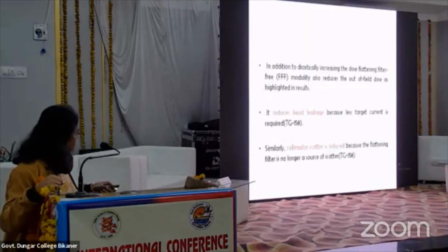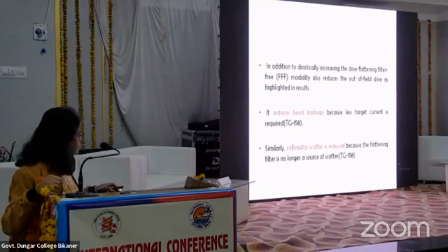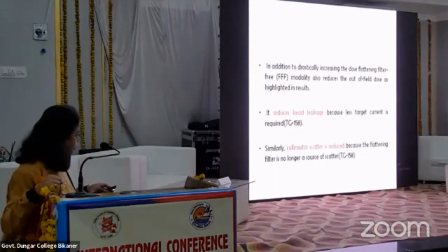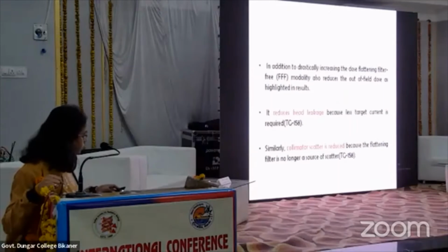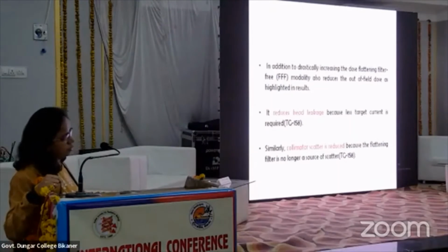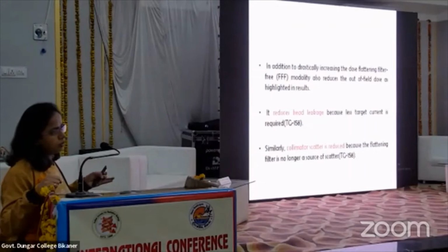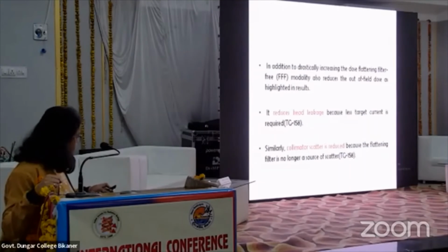So in addition to drastically increasing the dose, the flattening filter free modality also reduces the out of field dose, as highlighted in the results. Because it reduces the head leakage, since less target current is required in the triple F mode. Similarly, collimator scatter is also reduced, because the flattening filter is no longer a source of scatter. Since the flattening filter is removed, the main contribution from the collimator scatter is reduced.